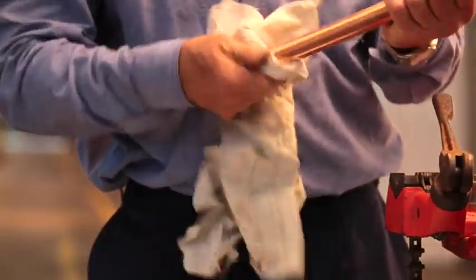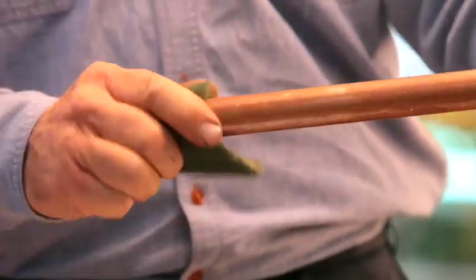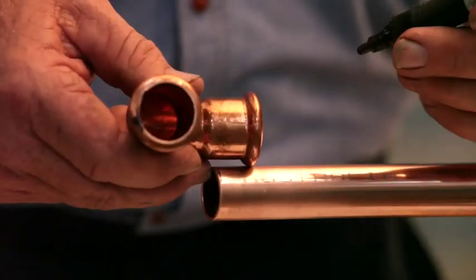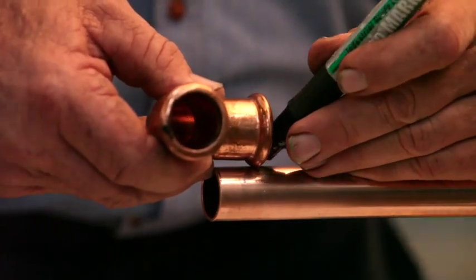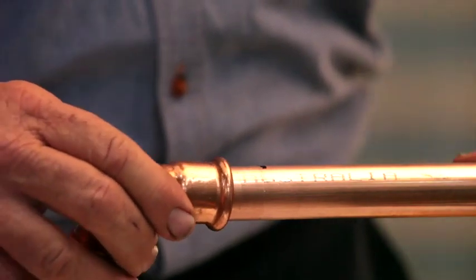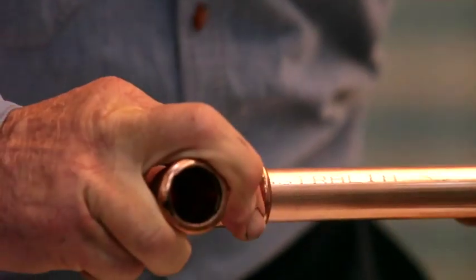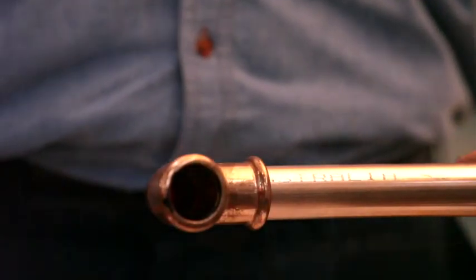When you are doing some maintenance and repair on some existing copper tube, clean the end with emery paper or a soft scourer. You can line up the tube and the fitting side by side and mark the tube. Push the end of the tube into the fitting by carefully rotating it until it reaches a complete stop. The outer edge of the fitting must line up with the marking.